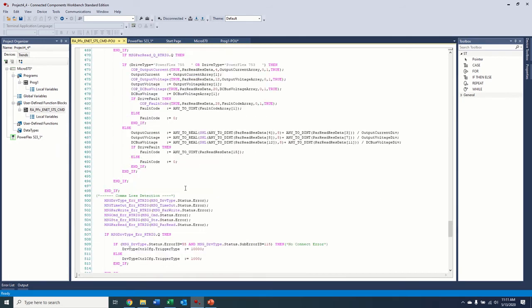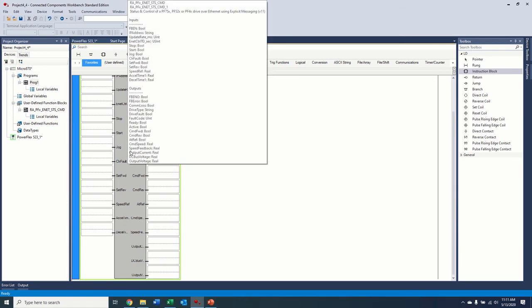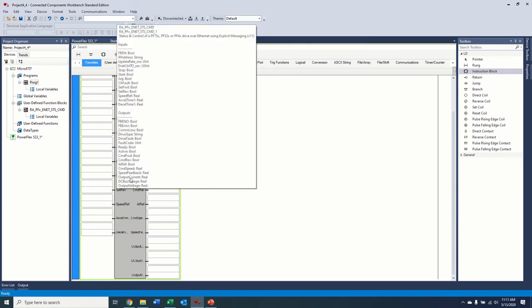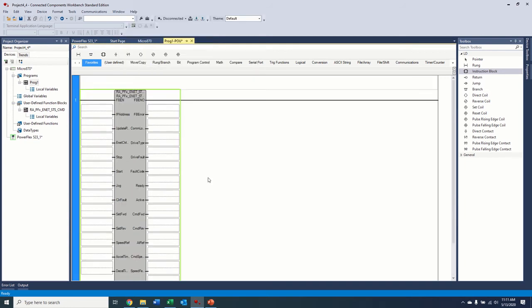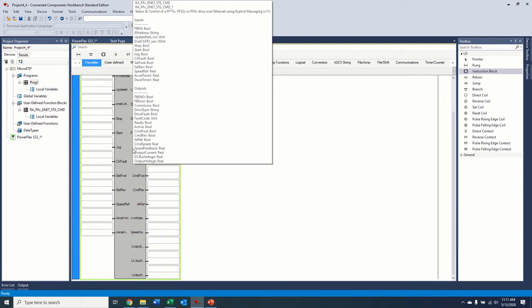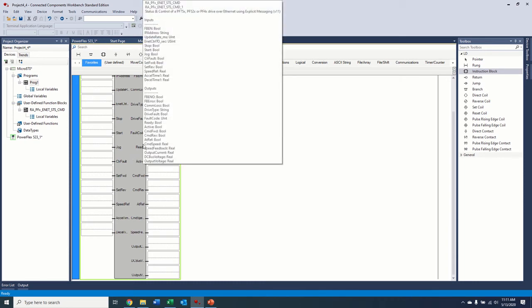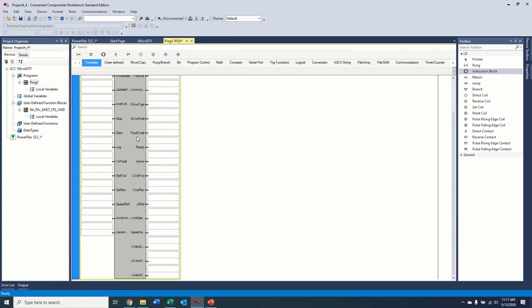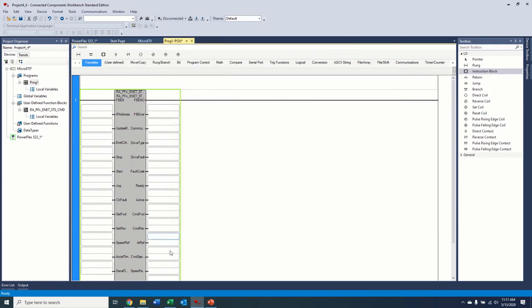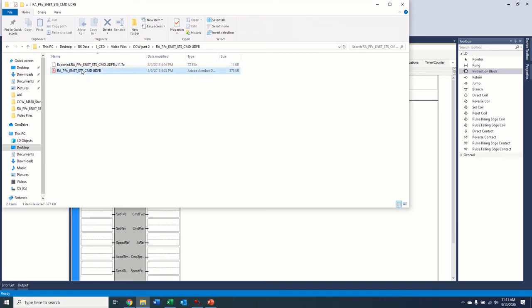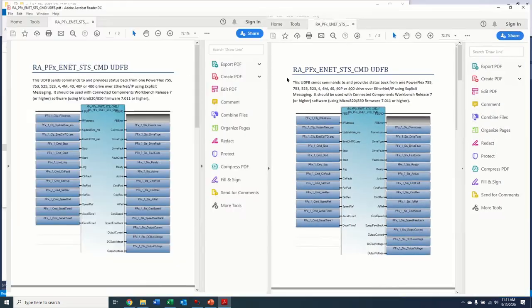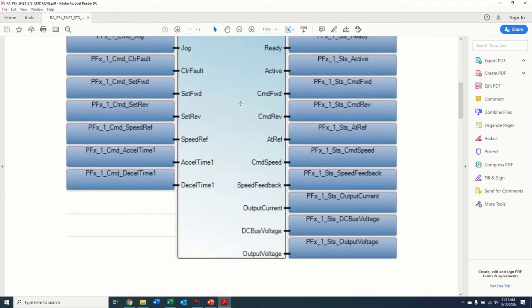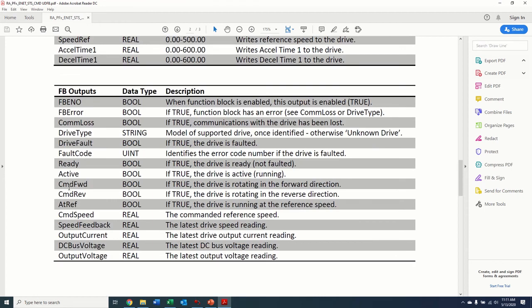Pretty much what it does is it just writes a lot of message commands back to the drive, or a couple of message commands back and forth to the drive to retrieve and set all of this information. So it's already done for you. All you need to do is handle the inputs and outputs and the tags going in. If you hover over the block, as you can see, it'll tell you what each of these are as far as data types as well, these tags. So what you need to create to be able to get the information into and out of the drive. Also, go back to your original folder where the 7z file was. There's this PDF that comes with it. It's just a short instruction set, shows you an example, and then a description of what each tag does.